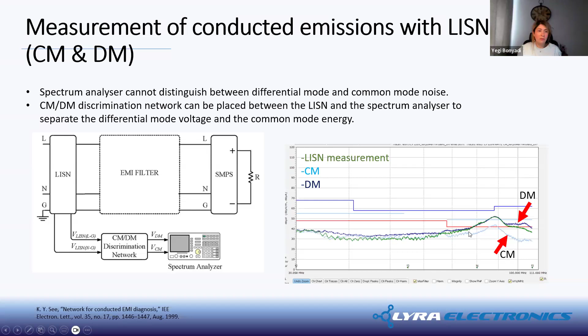As I mentioned, you can also use a current probe for doing your troubleshooting and testing. Both current probe and using a LISN show very similar results in low frequency, but in higher frequency above 5 megahertz, there can be some differences. And there are a few possible explanations for why these differences occur.